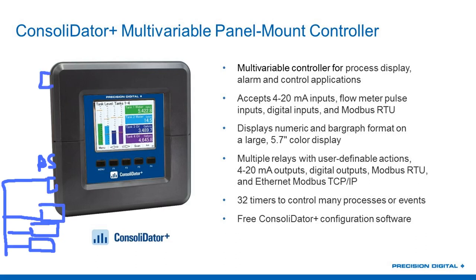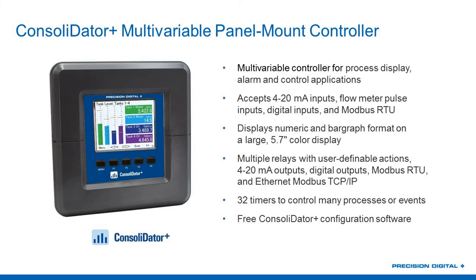Steve asks: can the Modbus server registers be mapped to TCP/IP? They cannot — all of these advanced features are only available on the RS-485 bus. That's great in that you can have the RS-485 bus doing all kinds of Modbus things as a master, spoofer, or snooper, while also having your Ethernet Modbus connected up pulling data into the company ERP system via the cloud. However, you can't plug in only Ethernet and have it start snooping through the Ethernet port. All the features discussed today are only available on the RS-485 connection, but you can also have the Consolidator Plus respond as a server to a client connecting via Modbus TCP/IP.